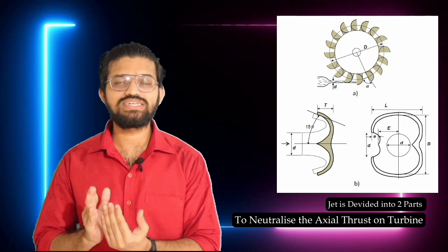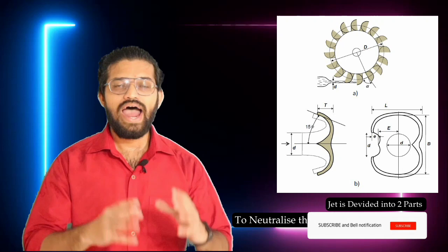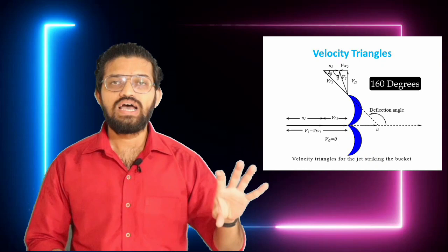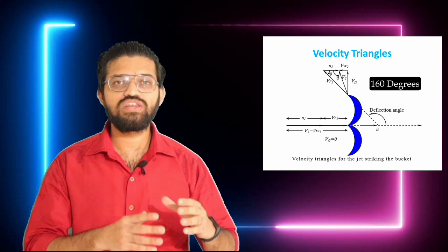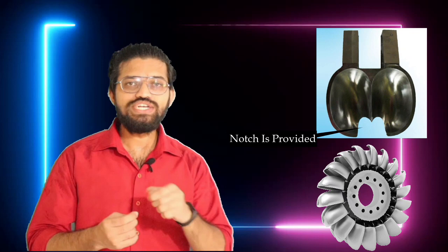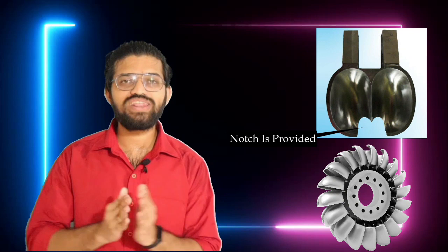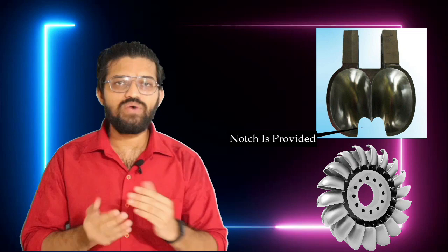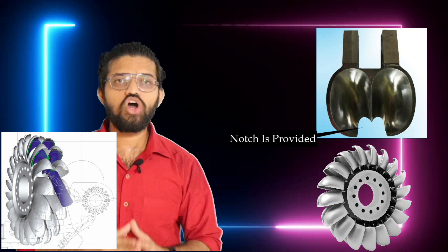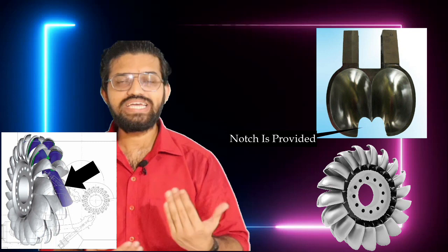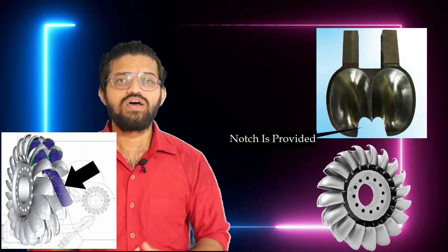The splitter divides the jet into two sections, and the jet is deflected at about 160 degrees, as you can see in this representation. Also, a slight notch is provided on each bucket. The main function of this notch is to ensure that when a bucket starts rotating, the next consecutive bucket is not affected by the incoming striking jet.